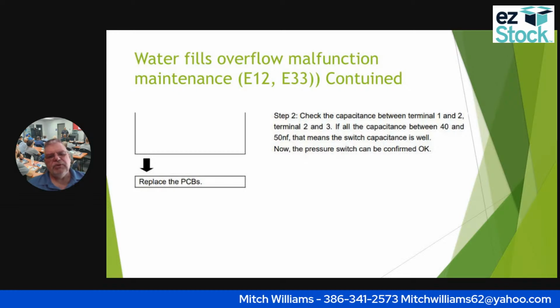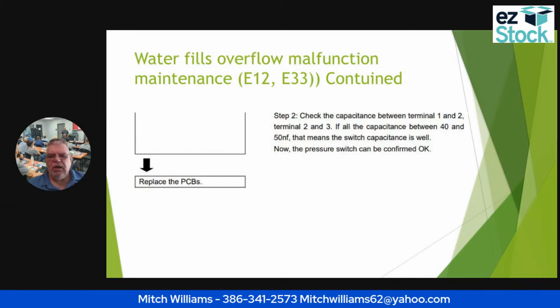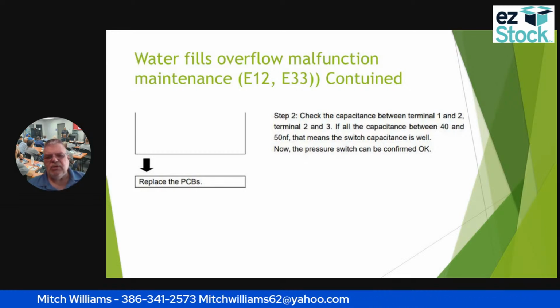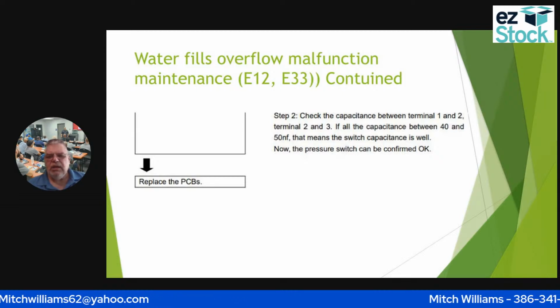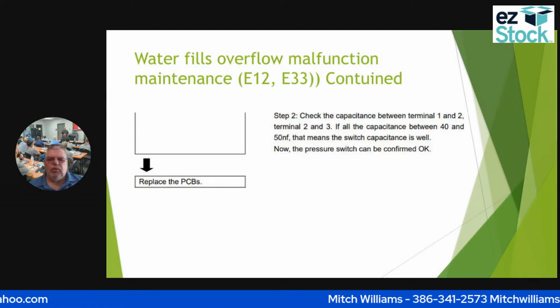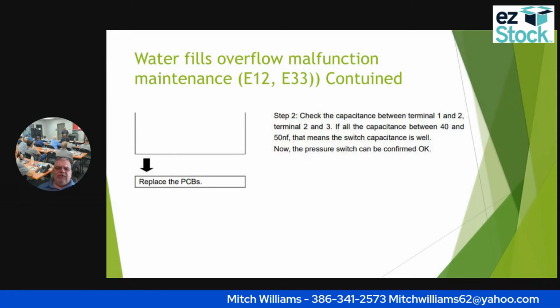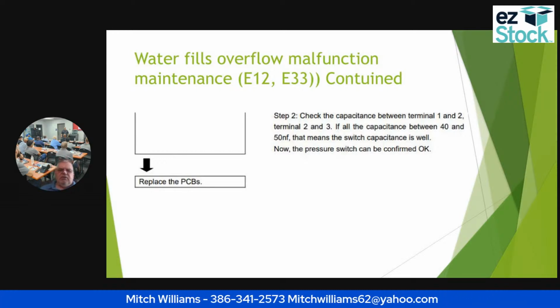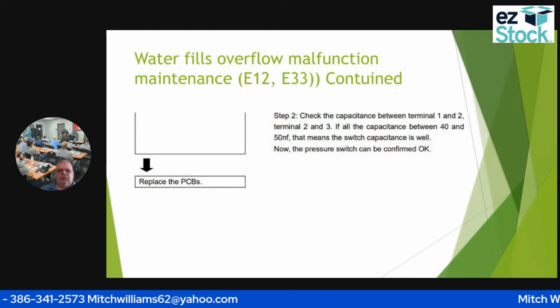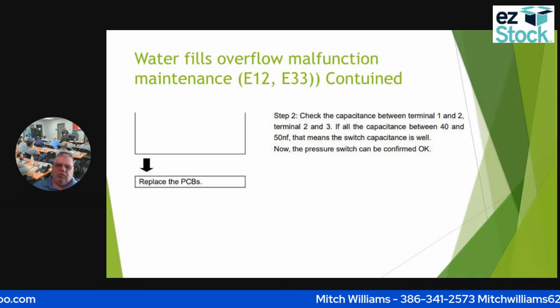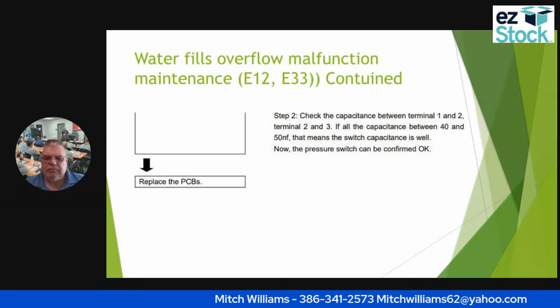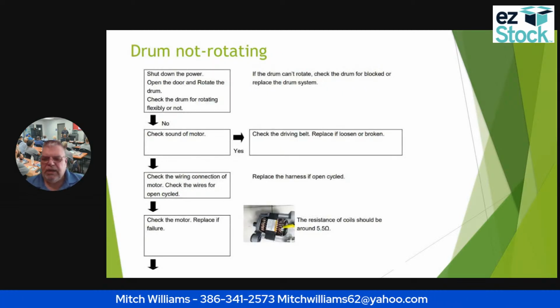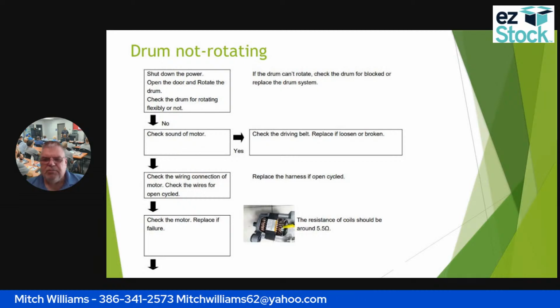Okay. If it overflows, I'm going to check the capacitance between terminal 1 and 2 and terminal 2 and 3. If all the capacitance is between 40 and 50, that means that the switch is acceptable, and the pressure switch is now confirmed that it works. If that's the case, then I'm going to replace the PCB. Okay, I'm going to stop right here for just a minute.